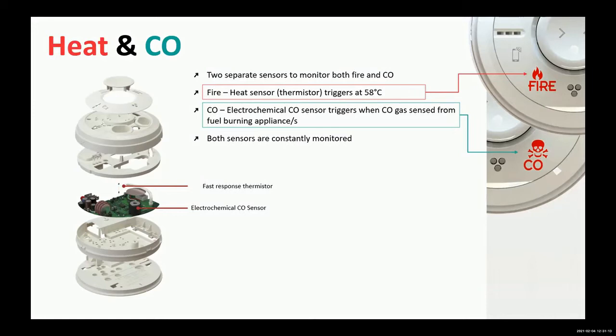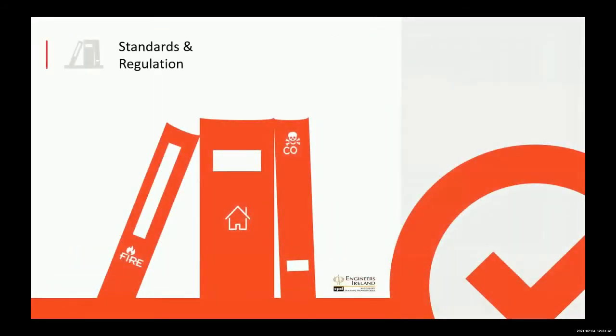And also, what we'd always promote as well, if you are mixing the systems, mixing fire with CO, adding them onto the same system, you should also always use a control switch on the system itself. For example, if you have a control switch, that will indicate which device is activated by just turning off all the other units and just leaving the one unit that has activated the system on. Okay, that's the sensors covered, and we'll do a bit now on the standards and regulations.